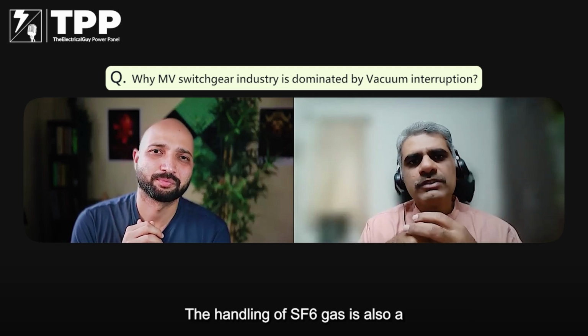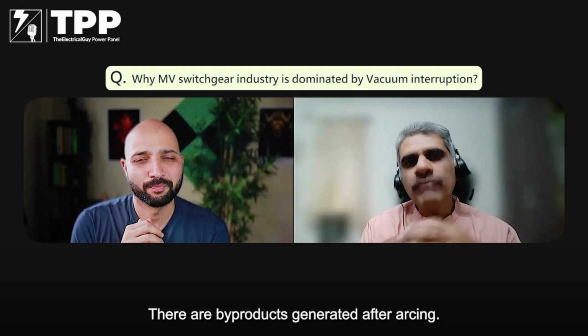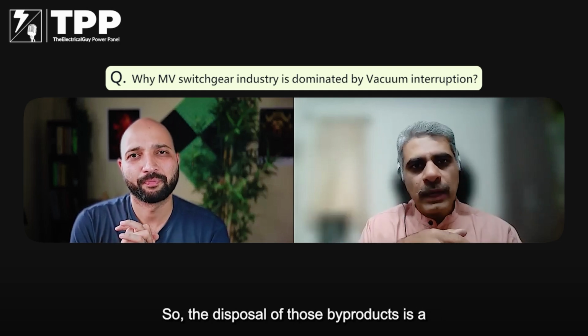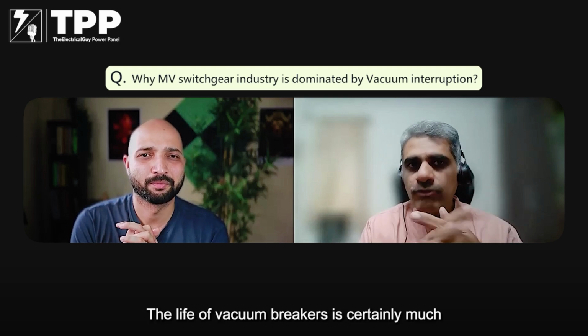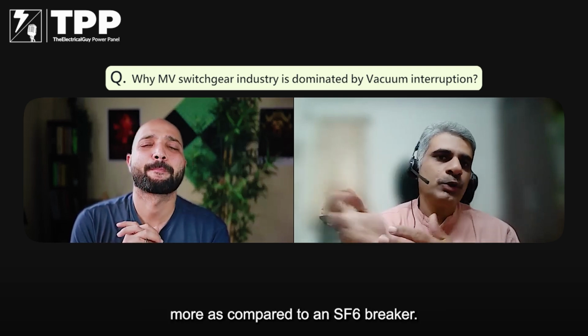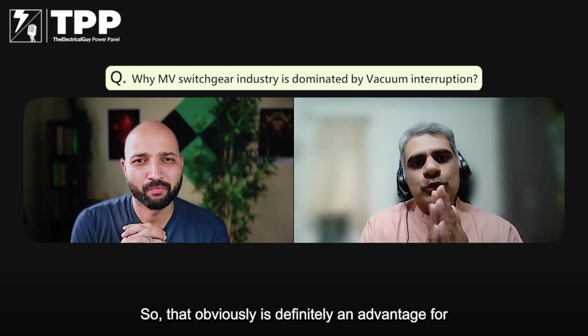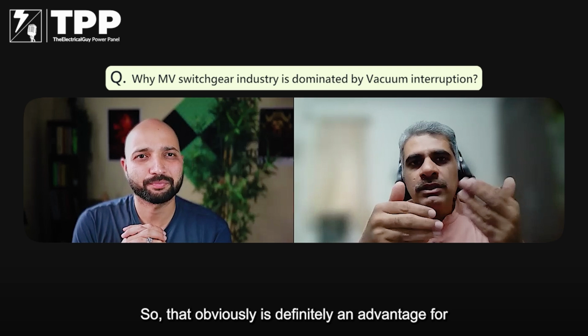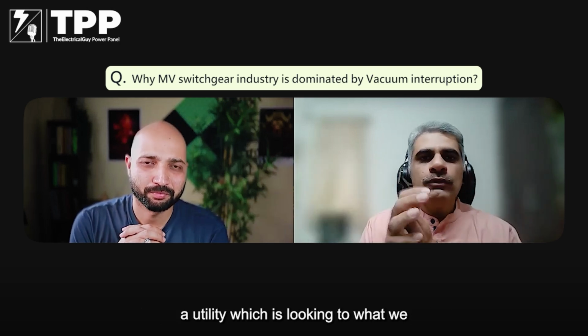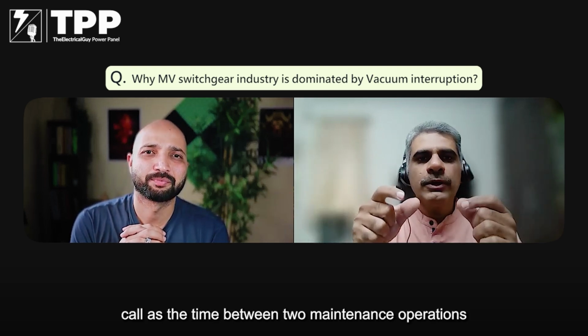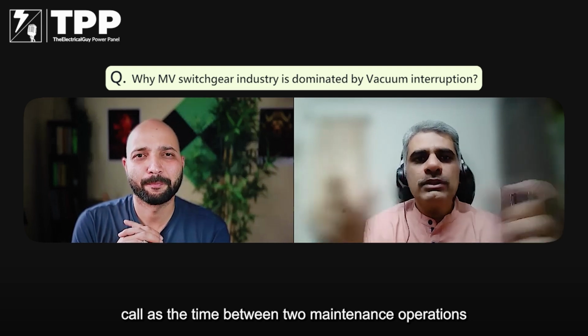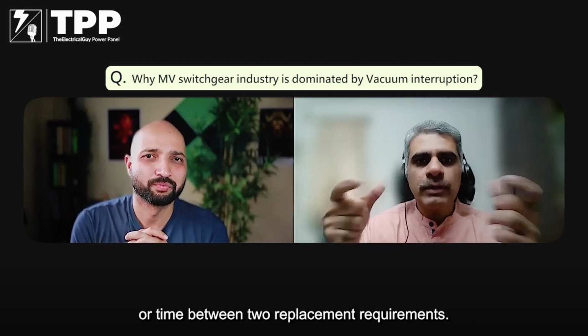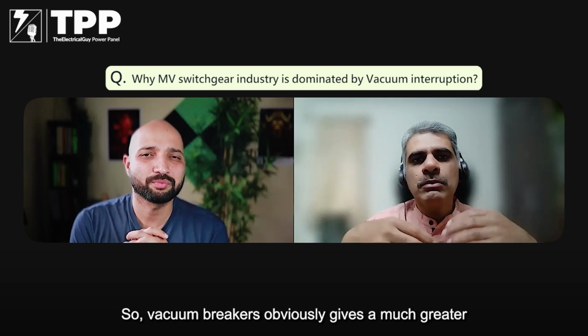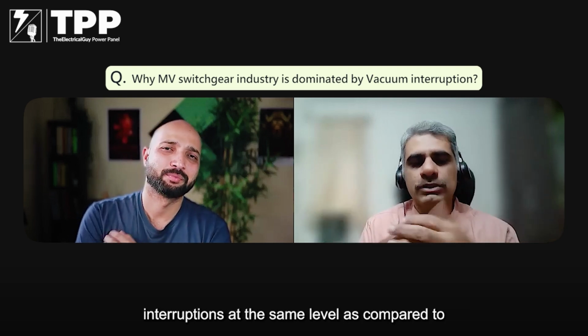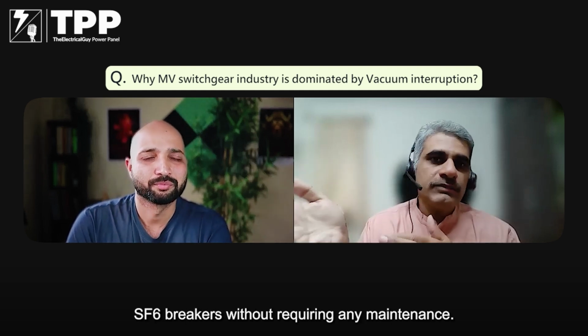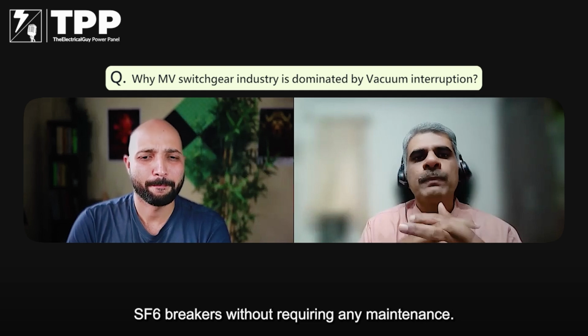The handling of SF6 gas is also a challenge. There are byproducts generated after arcing, so the disposal of those byproducts is a challenge. The life of vacuum breakers is certainly much more as compared to an SF6 breaker. So that obviously is definitely an advantage for a utility, which is looking at the time between two maintenance operations or the time between two replacement requirements. So vacuum breakers give a much greater life in terms of the number of current interruptions at the same level as compared to SF6 breakers, without requiring any maintenance.